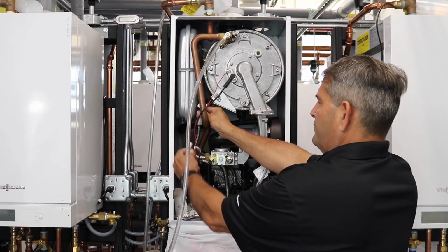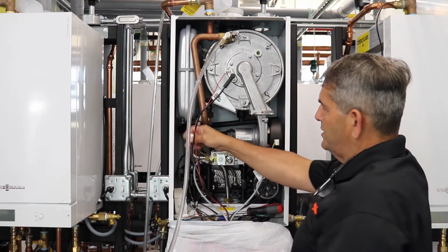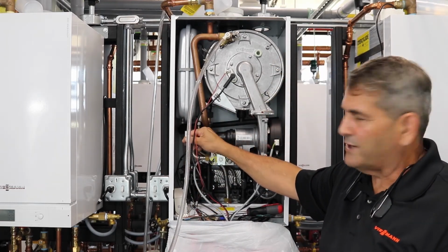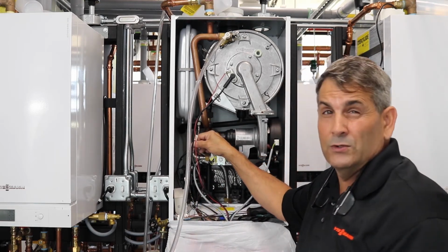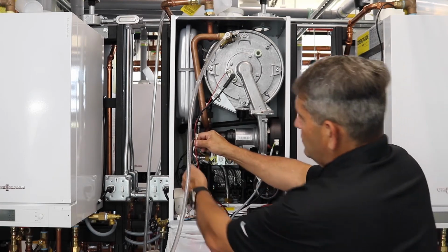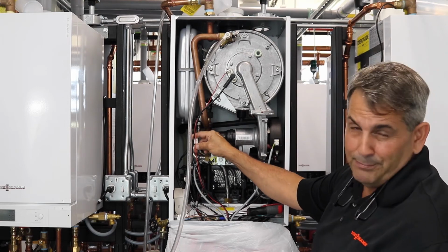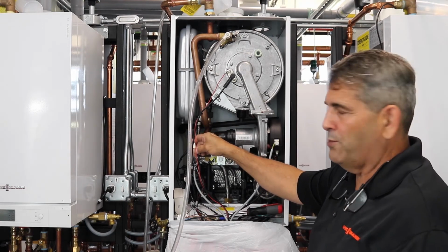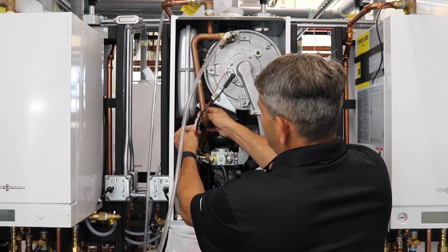Remember, it's plug 33. If it's not the switch here, you can also do a continuity check from your wire here. You're going to have to follow your wires back into the control itself and then find the 2 wires in there and do a continuity check, or just do a physical check on the wires to make sure it didn't get pulled out of the plug somehow, or a mouse chewed on the wire itself. Things you can check. Once we do that, we're just going to plug back in here.